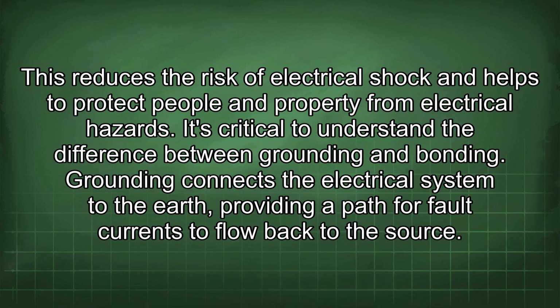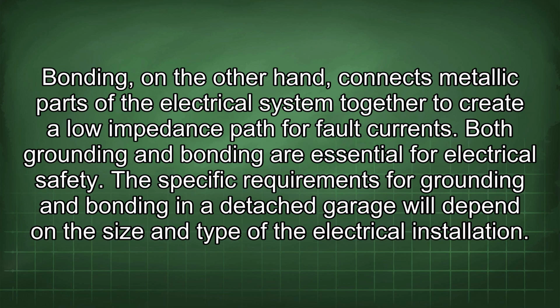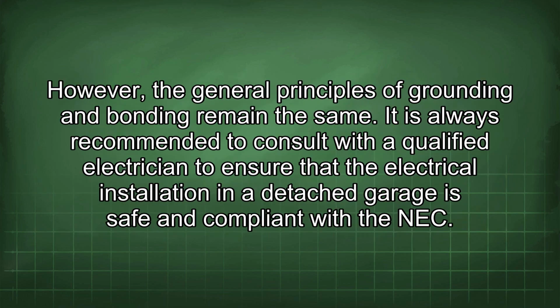It's critical to understand the difference between grounding and bonding. Grounding connects the electrical system to the earth, providing a path for fault currents to flow back to the source. Bonding, on the other hand, connects metallic parts of the electrical system together to create a low impedance path for fault currents. Both grounding and bonding are essential for electrical safety. The specific requirements for grounding and bonding in a detached garage will depend on the size and type of the electrical installation. However, the general principles of grounding and bonding remain the same. It is always recommended to consult with a qualified electrician to ensure that the electrical installation in a detached garage is safe and compliant with the NEC.